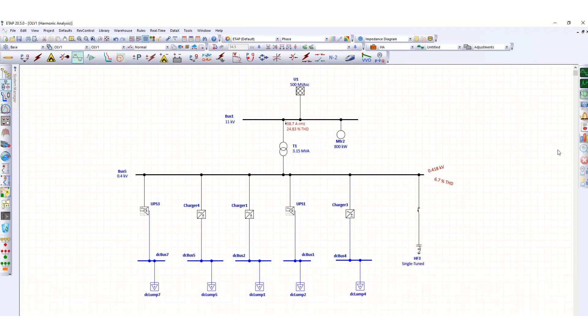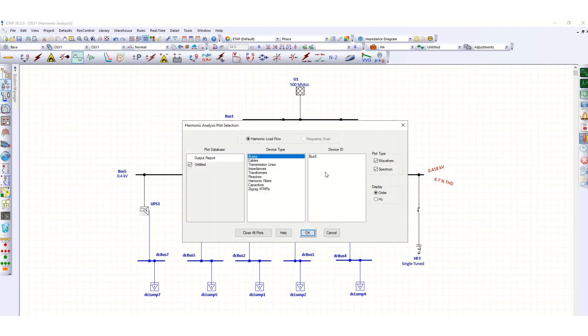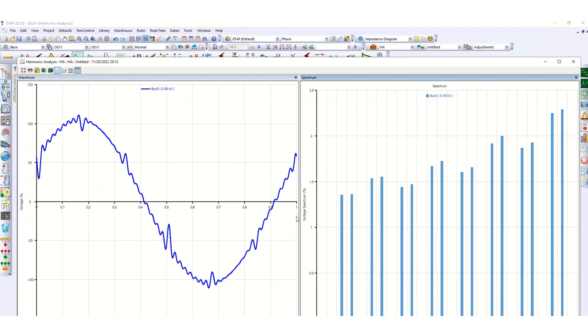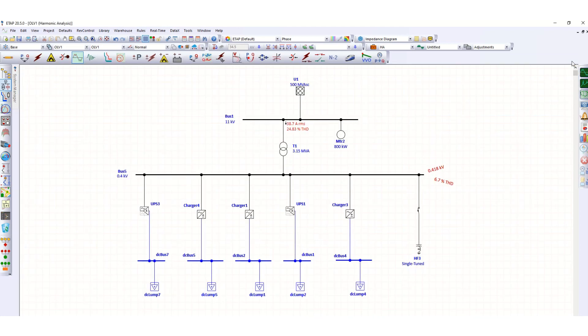If you plot here bus 5, click OK, you can see there is an improvement in this waveform with respect to the previous one.